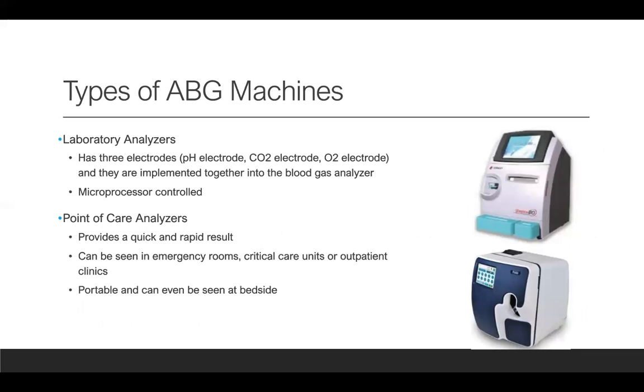Types of ABG machines. So there's two main types, but there's a lot of different brands. The laboratory analyzers are the first one, and this one is what we normally see in hospitals. This is probably the one that we've been working with the most in our clinical settings. It's the one that has the three electrodes that I just talked about, the pH, the CO2, and the O2, and they are implemented together into the blood gas analyzer. And it is also microprocessor controlled.